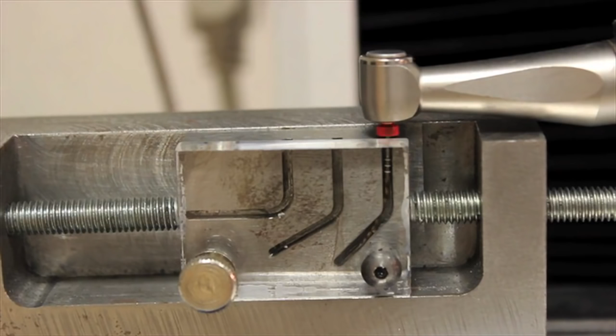These are the photos of the instrument machine and the stainless steel jig, as you can see here. And I'm showing you right now the last seconds of the cyclic fatigue test. And why the last seconds of the cyclic fatigue test? Because that's how long it took this instrument to fail on the cyclic fatigue. These are the numbers of the cyclic fatigue test. This is the maximum load in newtons that they apply until the instrument failed.